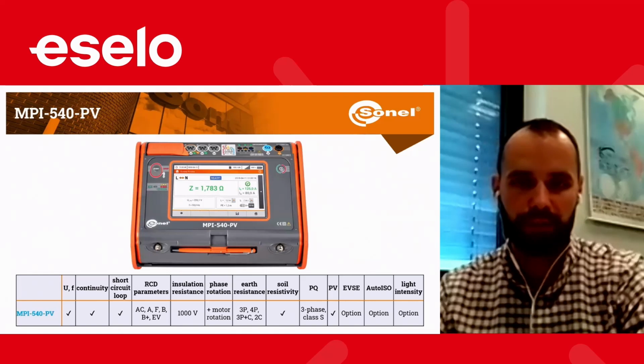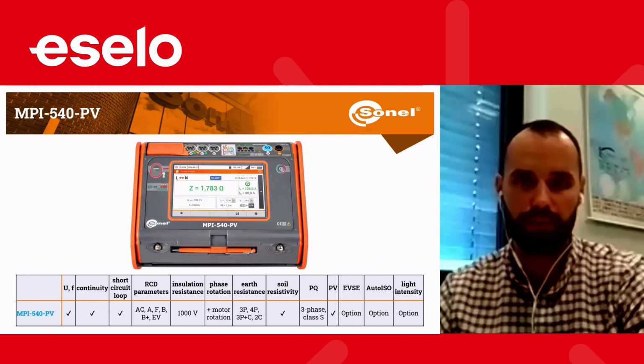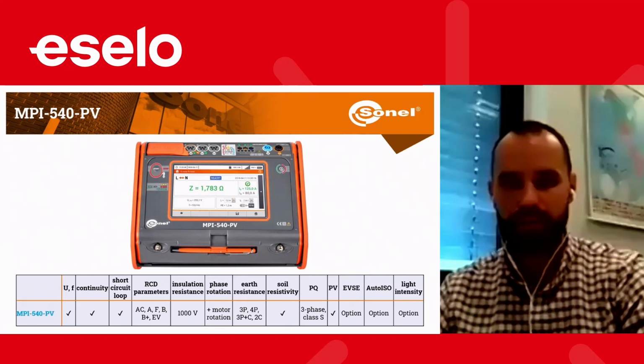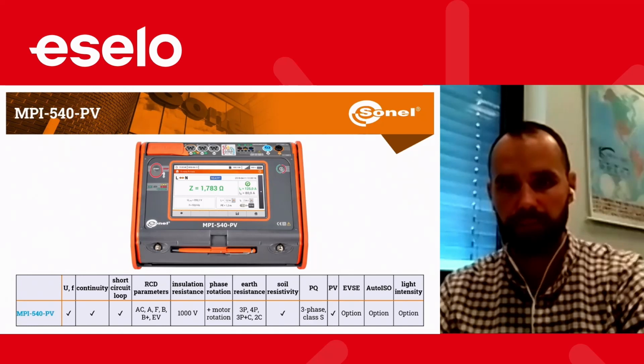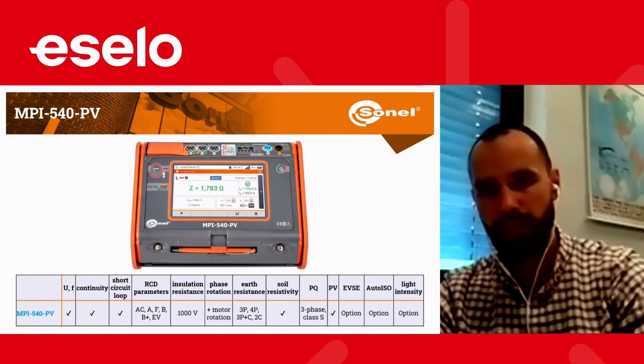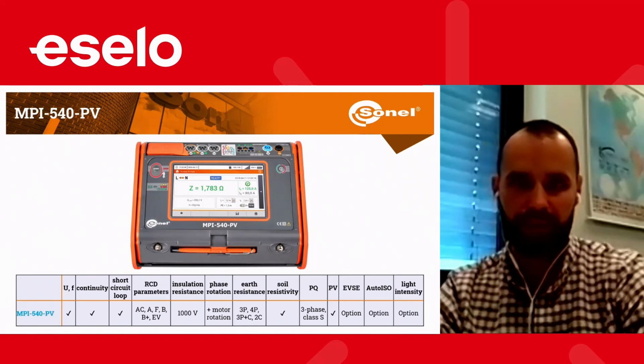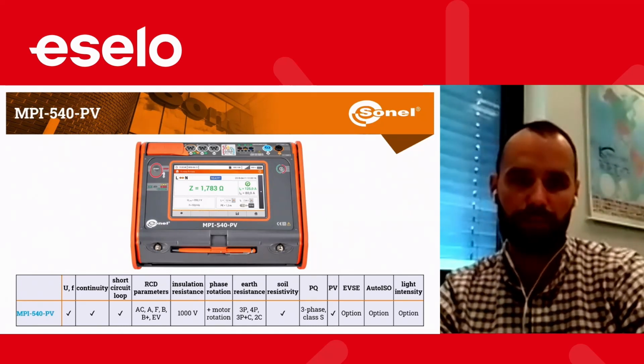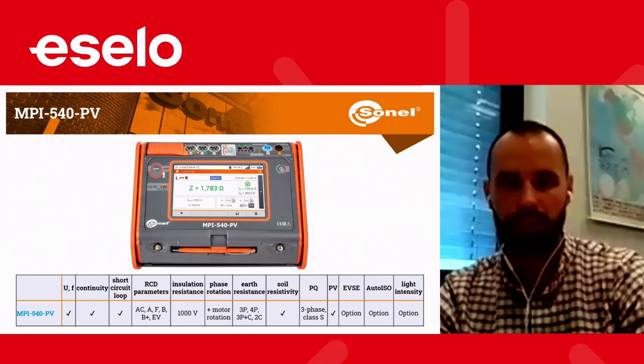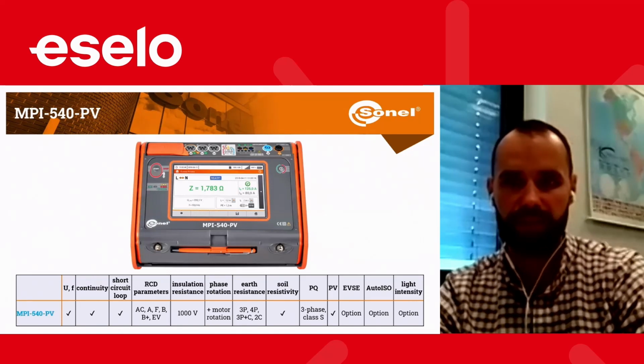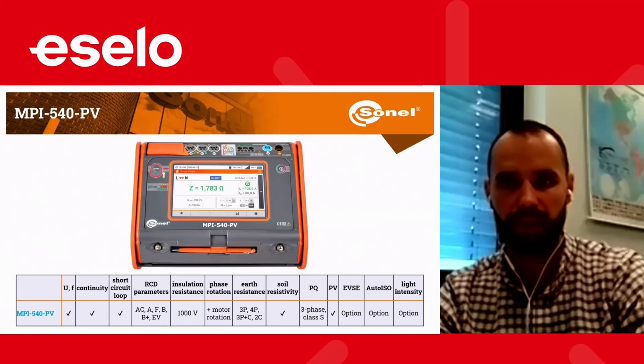Soil resistivity is very helpful to estimate what kind of grounding we will have to build in case the installation doesn't have grounding. We also have a power quality logger, 3-phase, in class S, and also the possibility to extend the measurements for other tests like EVSE test for electric vehicle charging, and some additional features like auto ISO and light intensity, which we use for estimation of the optimal condition of the test on the panel.